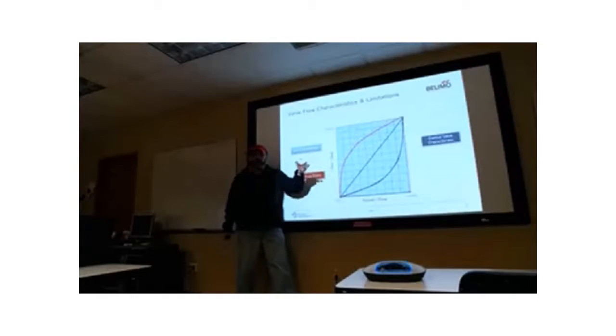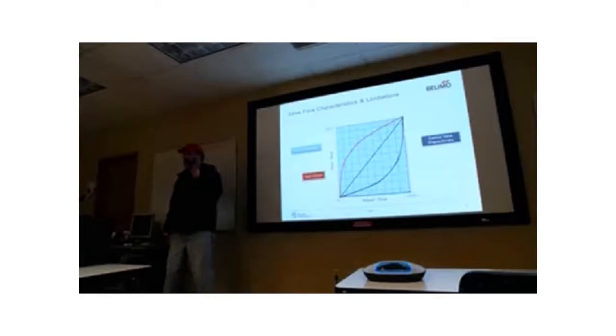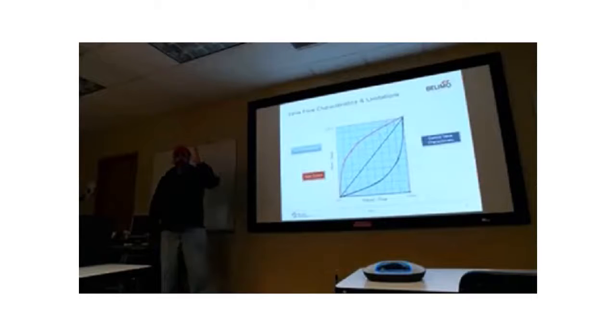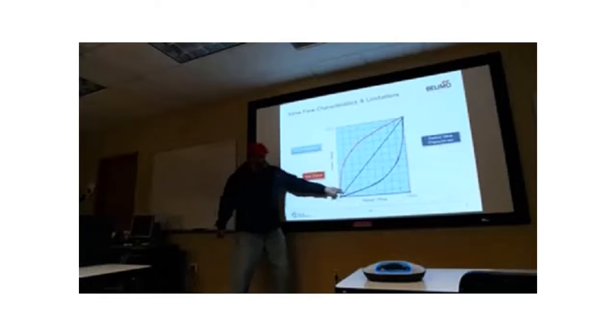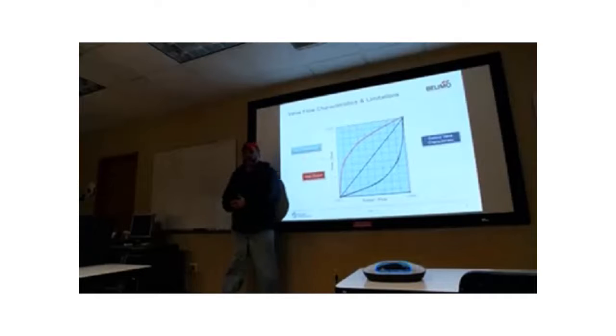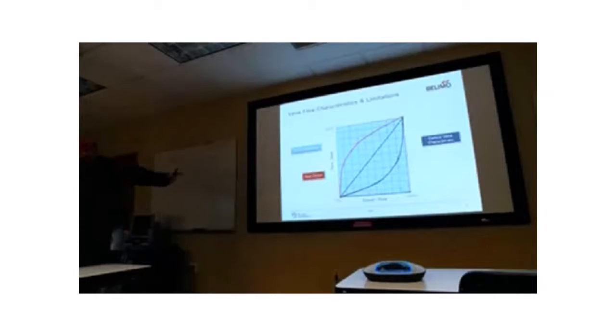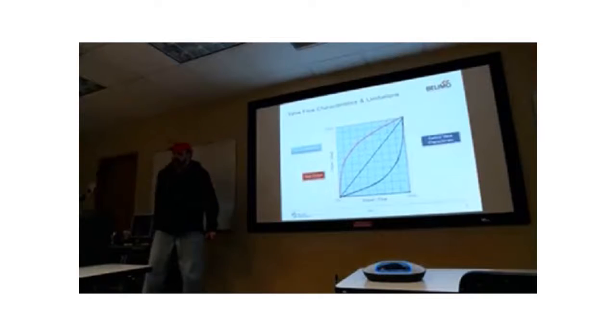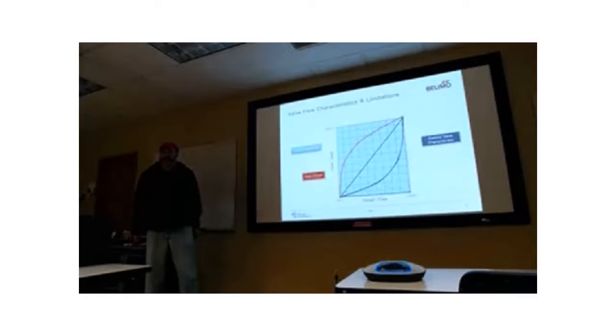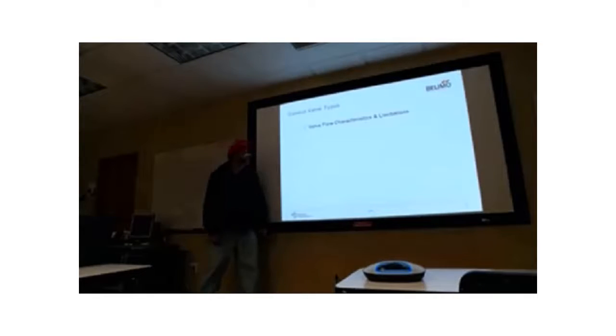Here's why you guys thought that a linear characteristic would work for water flow for coils: because you were thinking about water flow, right? We want the heat flow to be linear, right? We want the heat flow that goes in and out of that coil to be linear. Does that make sense? Not the water flow, but the heat flow. So that's why this characteristic looks so weird. You say, no way. But it all works out. This is why we make equal percentage valves. And if you understand this, you may understand more than most engineers under 3 years of experience, because they may not totally get this, but this is why we specify equal percentage valves.